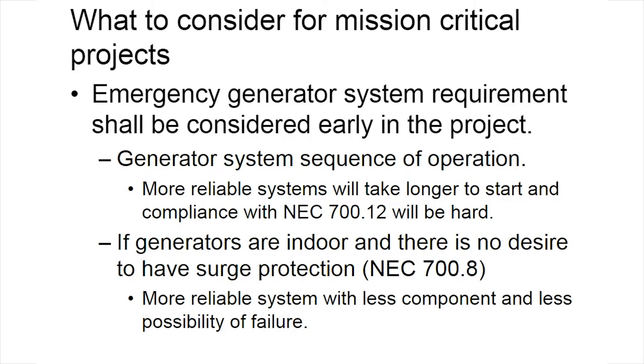That's why in many of these projects you will see UPSs, rotary devices, anything that will keep that load up for 30 seconds, 1 minute, 5 minutes, 10 minutes, even up to 15 minutes. I even heard up to 2 hours. So you ensure that your generators are on. It's a little bit different approach.